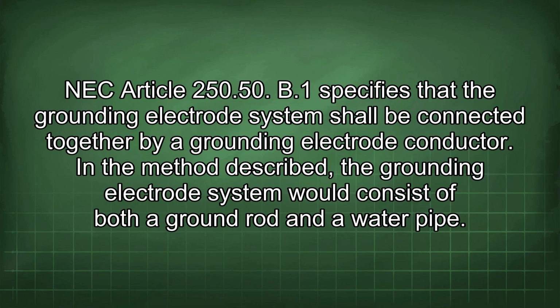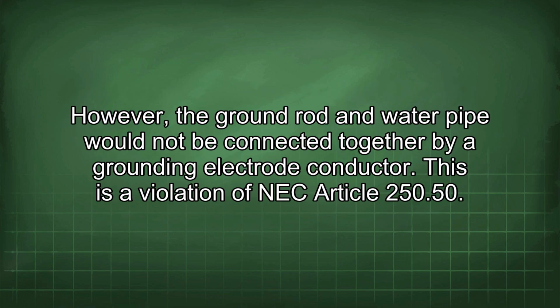NEC Article 250.50(1) specifies that the grounding electrode system shall be connected together by a grounding electrode conductor. In the method described, the grounding electrode system would consist of both a ground rod and a water pipe. However, the ground rod and water pipe would not be connected together by a grounding electrode conductor. This is a violation of NEC Article 250.50.